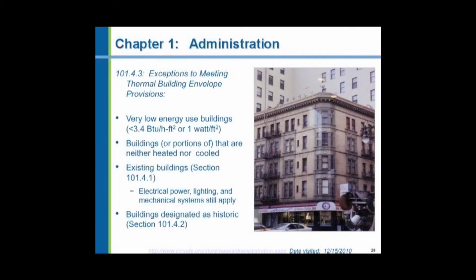And an existing building, if you're not touching the building, but you're going into the building and replacing furnaces or air conditioners, which is more frequent, you're going to do that every 15 to 20 years, you don't need to bring the building up to compliance with the envelope requirements, but you do have to install new appliances, heating and cooling appliances, that comply with the Federal Energy Code minimum efficiency standards. 80% for furnaces, 13 SEER for air conditioners, and 0.62 energy factor for water heaters.